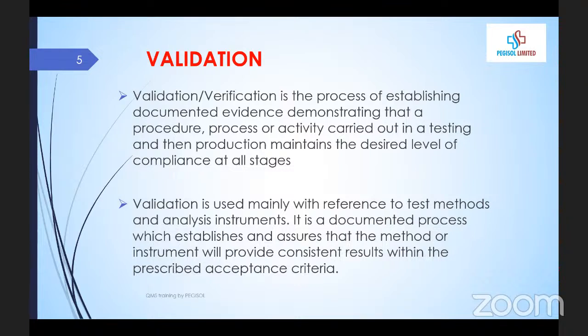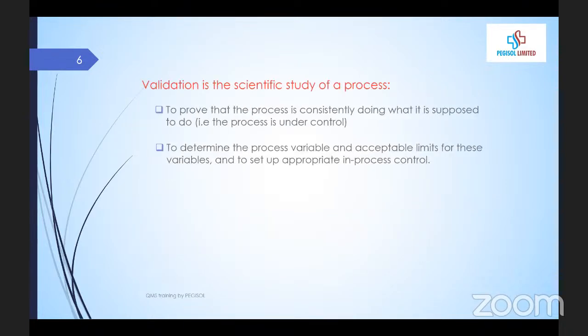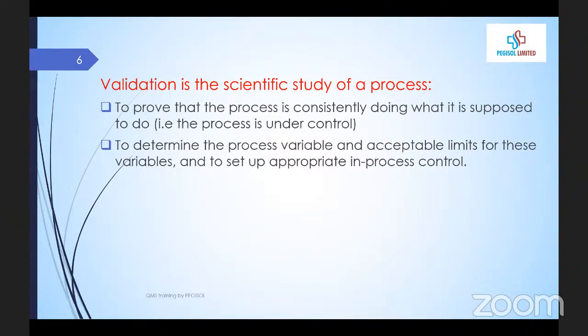Let's say, for example, you buy a new reagent. You shouldn't use that reagent until that reagent is validated, until that test is validated, until that equipment is validated, before you put it into patient use. Now, validation is a scientific study of the process to prove that the process is consistently doing what it's supposed to do, that the process is under control. So validation will help you to determine the process variables and acceptable limits for the variables, and to set up an appropriate in-process control for that process.